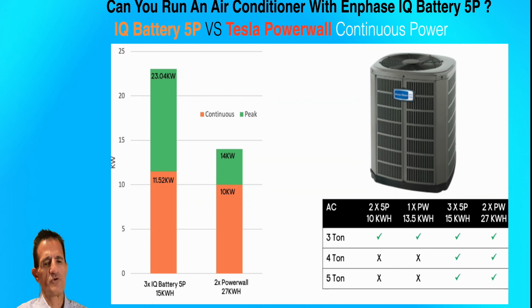But when we get to a 4-ton or 5-ton unit, you would need about 3 of the 5Ps, 15 kilowatt hour of batteries, or 2 of the Powerwalls at 27 kilowatt hour of batteries. The problem is you're buying more battery than you need just to meet that surge of power to run the air conditioner or heat pump.